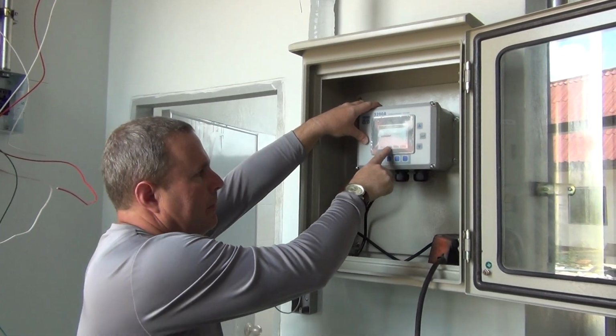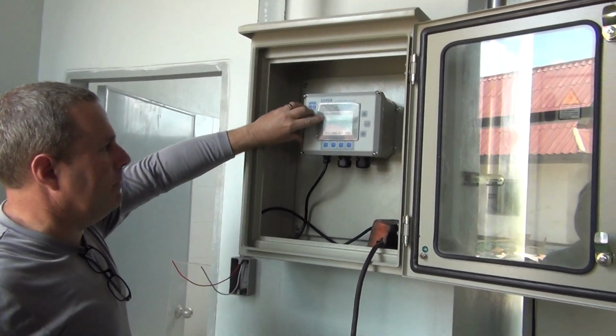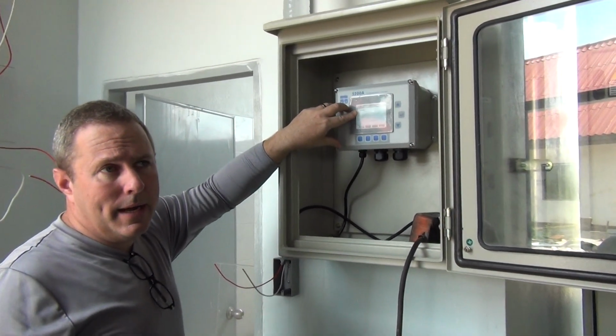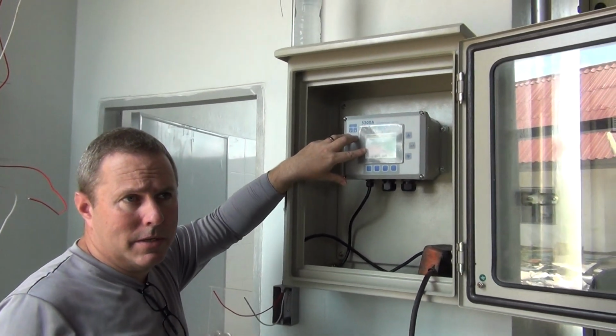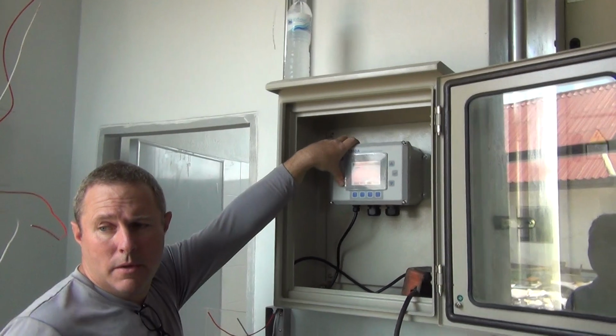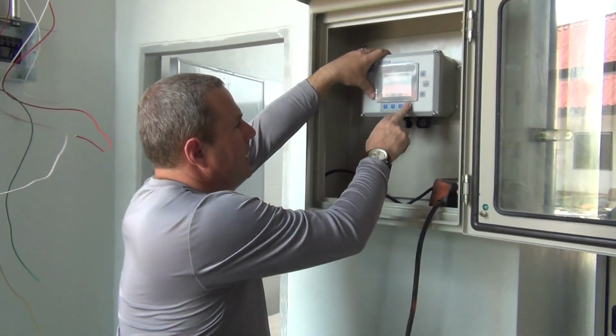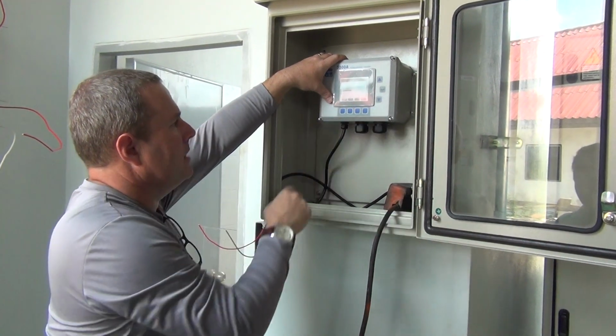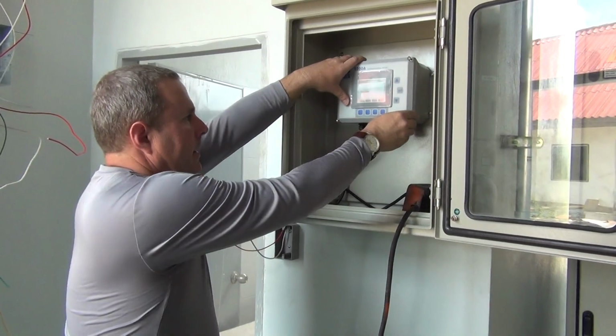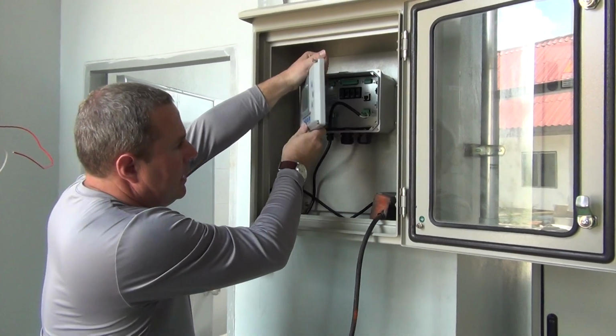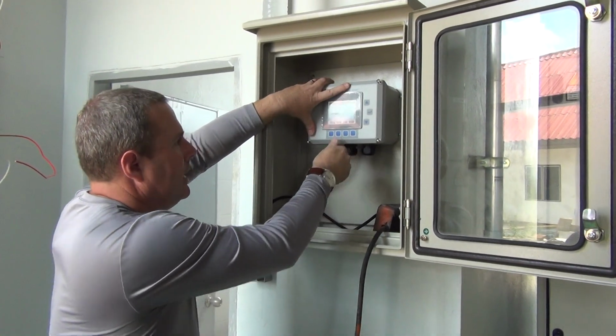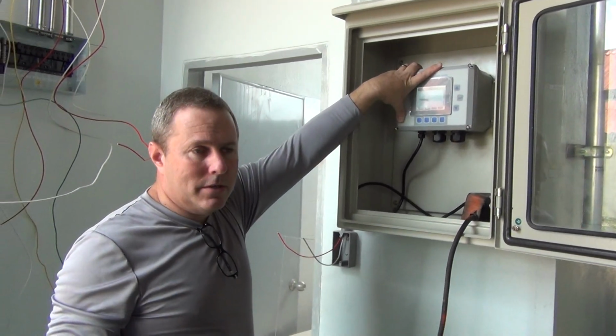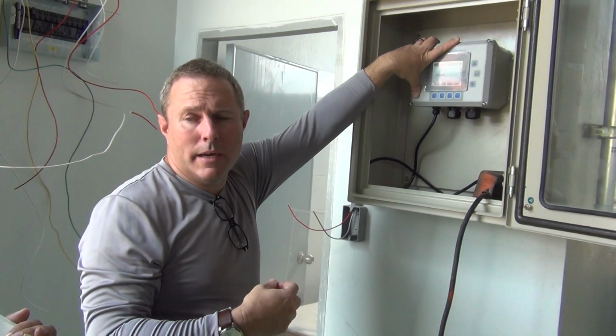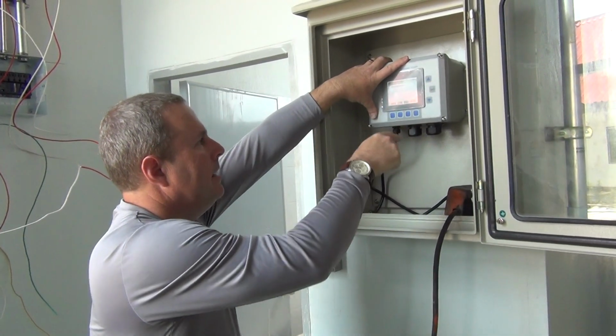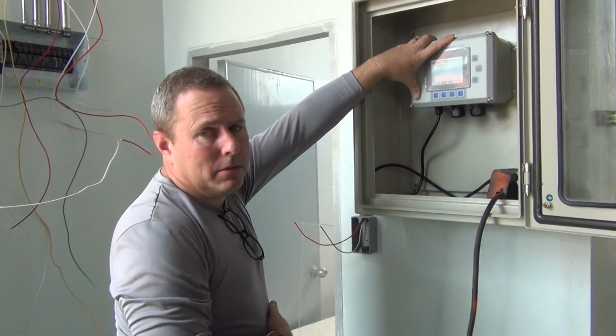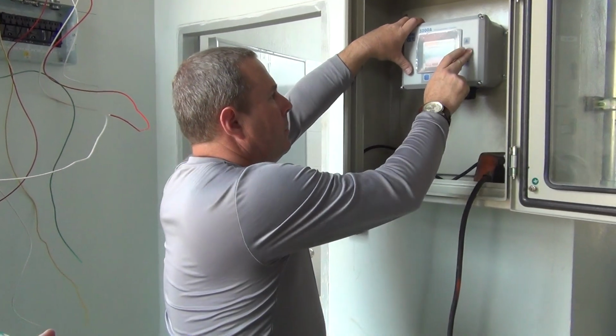Communications is where we were just a few minutes ago. Communications is where we set up the Ethernet, where we set up the RS-485, and where we set up the RS-232 serial port. So that is what the communications menu item is. The next item is going to be configure auxiliary. This is for the auxiliary inputs located here. And that is what would allow us to set up external devices, additional sensors, and other things that we may want to data log and control from. So we can press that, and you can see that both are currently disabled.